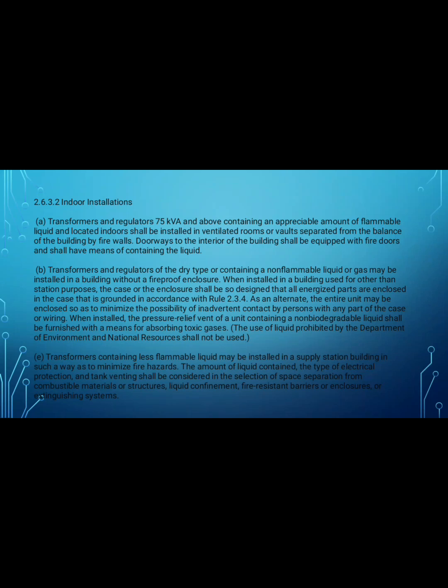When installed in a building used for other than station purposes, the case or enclosure shall be so designed that all energized parts are enclosed, and the case is grounded in accordance with Rule 2.3.4. As an alternate, the entire unit may be enclosed so as to minimize the possibility of inadvertent contact by persons with any part of the case or wiring. When installed, the pressure relief vent of a unit containing a non-biodegradable liquid shall be furnished with a means for absorbing toxic gases. The use of liquid prohibited by the Department of Environment and Natural Resources shall not be allowed.